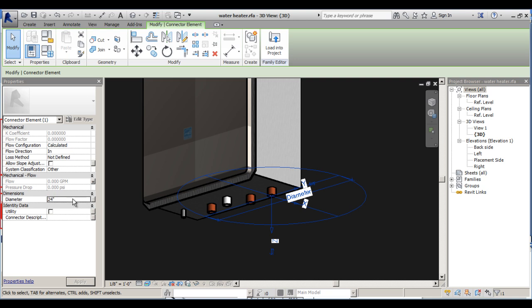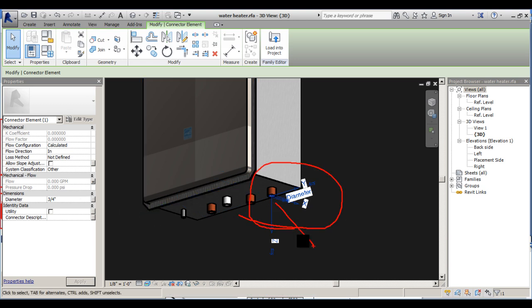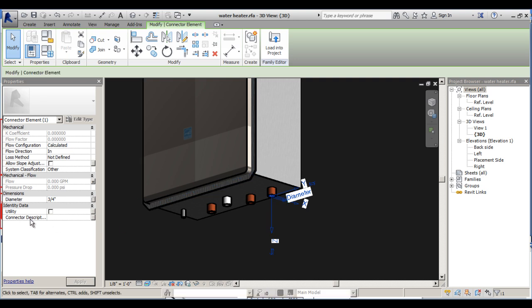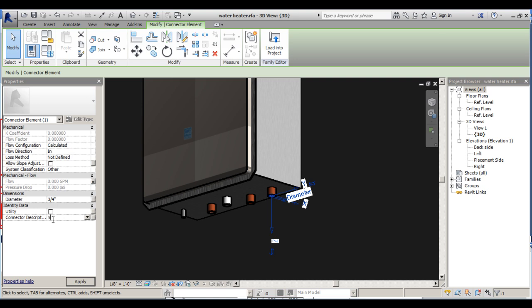Diameter is very important. This is where we set the diameter of what type of pipe can connect to this connector. In this case we're working with a three-quarter inch pipe. When I accept the value, the connector changes size in the model — this is normal. Lastly, I'll set a connector description and place 'natural gas' here to indicate the system we're working with.